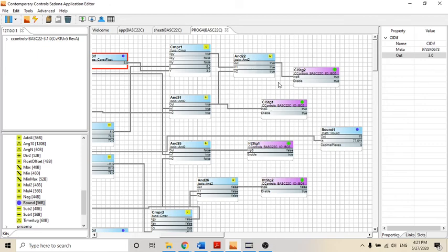higher temperature than the set point, and therefore we're going to have cooling stage 2 go on. The minute that lowers again, which we will see on our temperature, the minute that lowers again and becomes 3 or less, then our cooling stage 2 will go off and only cooling stage 1 will remain.